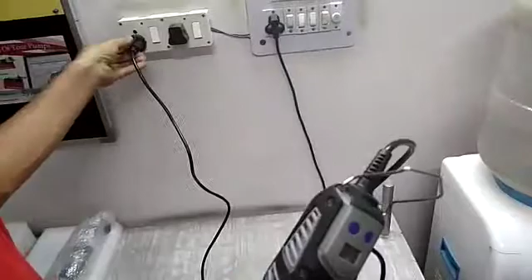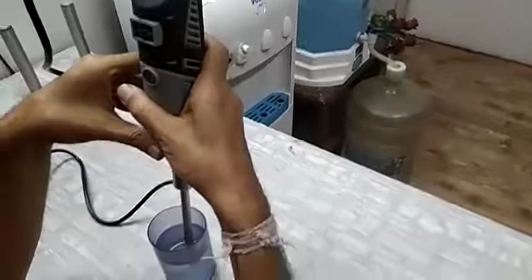Before putting the switch on, insert your probe into the sample. The probe should be inserted into the sample around 1 to 2 inches or maximum half of the probe length, not more than that. Maybe you can tilt it slightly at an angle of 45 degrees, which gives better lysing for the tissues. Also, one important thing is that once you run the machine, your tissue samples should be chopped small so that they enter into these slits. If the tissue samples do not enter these slits, your lysing will not be good. So you should chop the tissues smaller than 1 mm cross section.